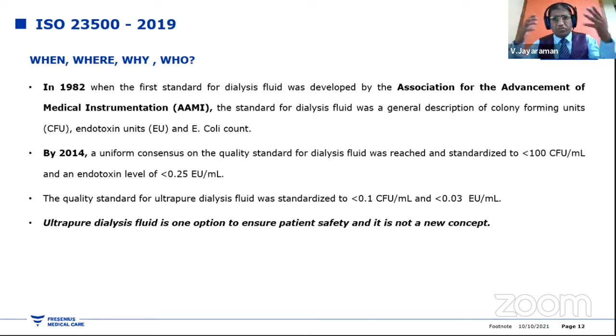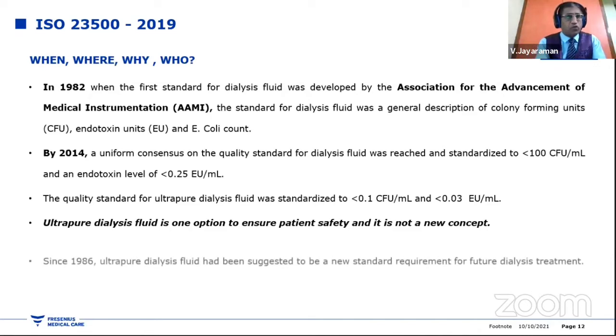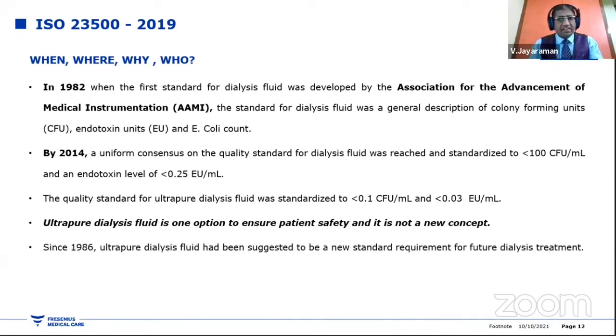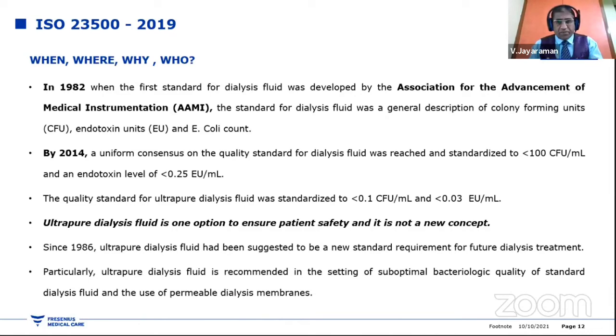But this ultra pure dialysis fluid is not just a new concept. I have been in this field from 87, and I have seen in the late 90s the endotoxin retention filters were there at the rear end of the machine. This was able to ensure, if you have the ISO quality of water and the concentrates mixed in the various ratios, delivery of ultra pure dialysis fluid. Last but not least, in 1986, the ultra pure dialysis fluid was suggested to be a new standard. Particularly, ultra pure dialysis is recommended not just for online hemodiafiltration, but even for standard hemodialysis.